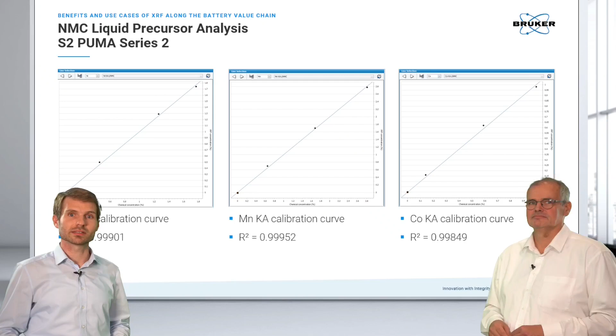There's a snapshot from our software, left-hand side. You see how the results can appear. You can, like Kai said, express that as concentrations, elemental concentrations, oxide concentrations, whatever you find more fitting. You can also transfer this into maybe a more useful space for you. So you can transfer this into the molar ratios according to the NMC type. So you can, for example, say, oh, you have a 6 to 2 to 2 type, how close you are to the 6, to the 2, to the 2. And based on that, you can determine thresholds. So for the operator, it's very easy to make a decision based on the threshold. If something red pops up, it means simply out of spec, we have to do something, whatever our standard operating procedure defines.